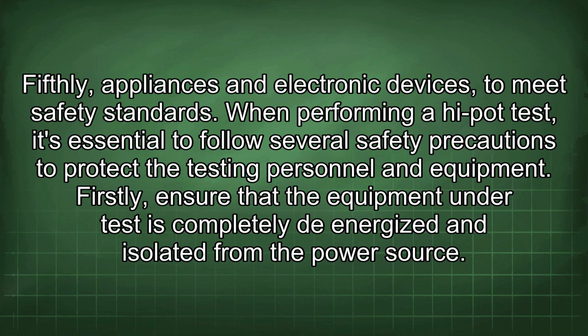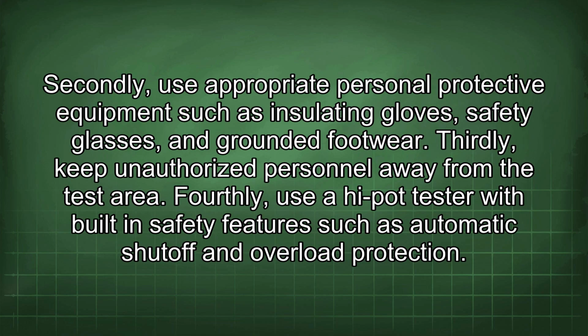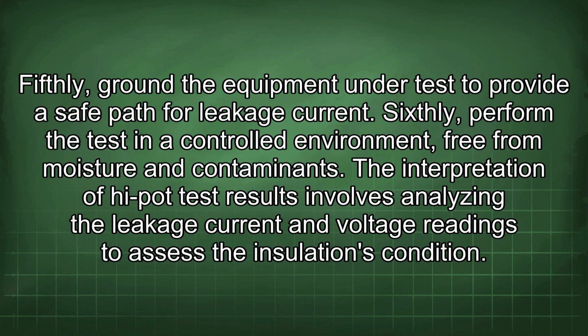When performing a hi-pot test, it's essential to follow several safety precautions to protect the testing personnel and equipment. Firstly, ensure that the equipment under test is completely de-energized and isolated from the power source. Secondly, use appropriate personal protective equipment such as insulating gloves, safety glasses, and grounded footwear. Thirdly, keep unauthorized personnel away from the test area. Fourthly, use a hi-pot tester with built-in safety features such as automatic shut-off and overload protection. Fifthly, ground the equipment under test to provide a safe path for leakage current. Sixthly, perform the test in a controlled environment free from moisture and contaminants.